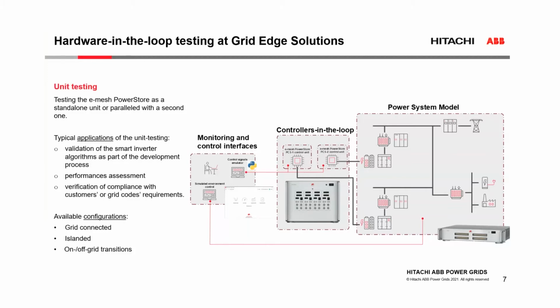An example is that we have used hardware-in-the-loop testing as a pre-assessment before starting the real testing for grid code compliance of our power store against several grid codes, especially in Europe. With this method, we've been able to address any possible issue uncovered during hardware-in-the-loop testing, and minimize the real testing time during certification.